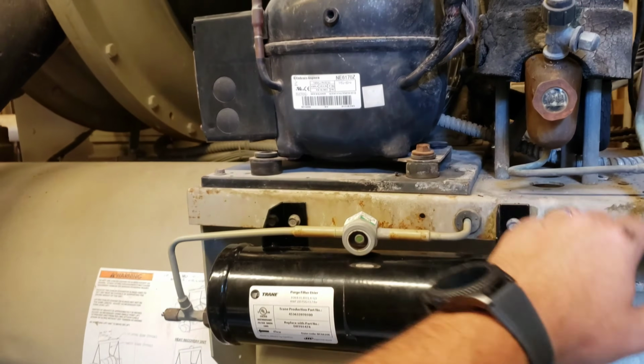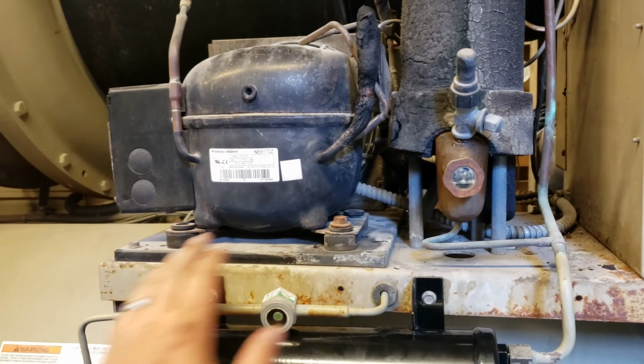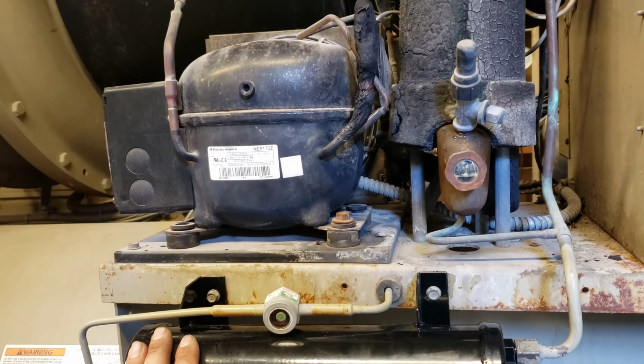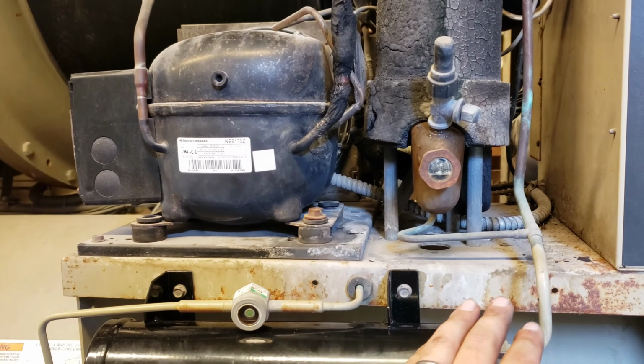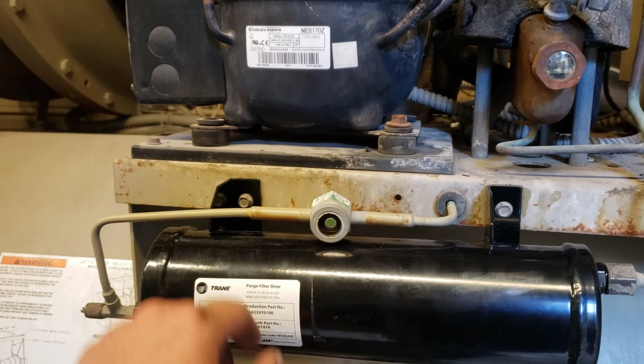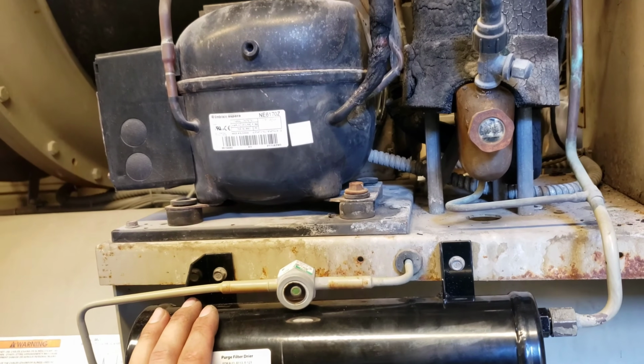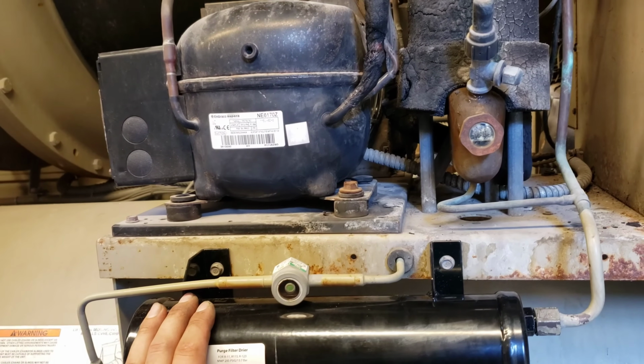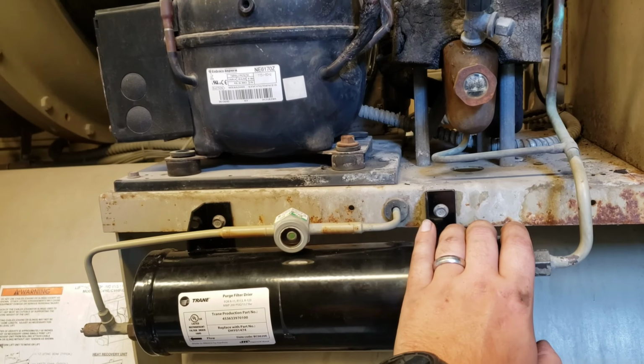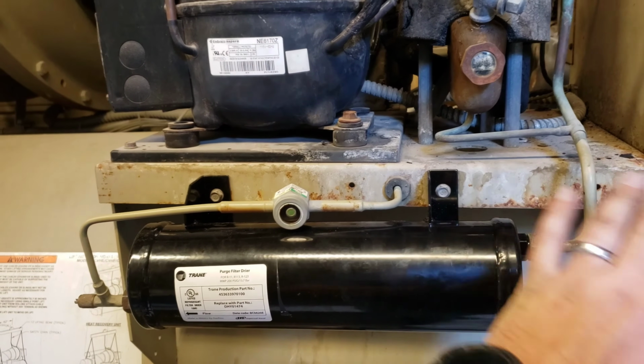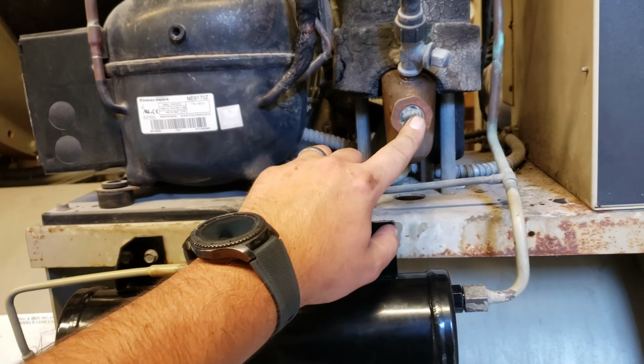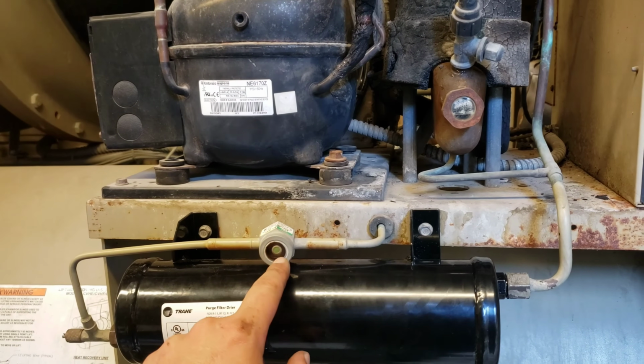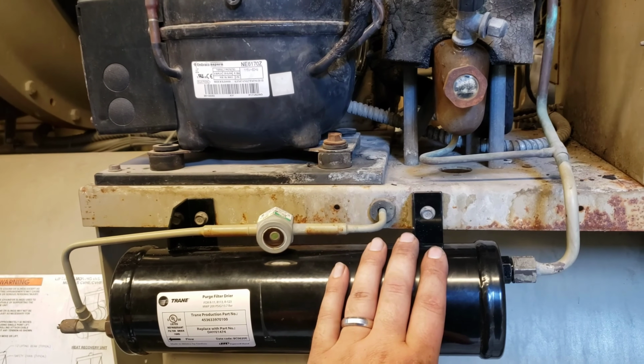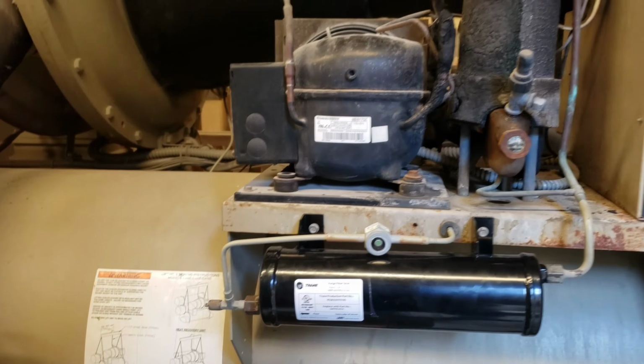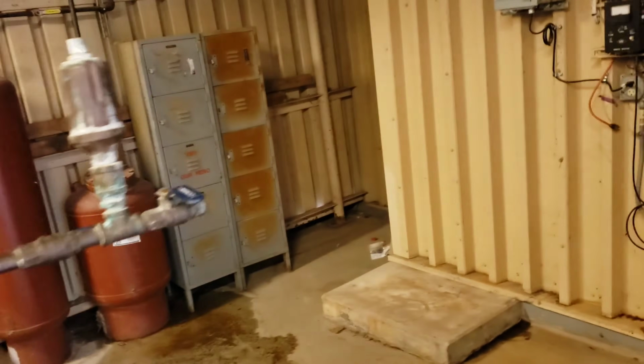Anyway, on top of that, even after I got the purge running, I was not draining the liquid off of the tank like I was supposed to. And come to look at the date code, the date code on the purge filter was from 2014. Well, it's 2020. So I already had the new filter ready to go. I just hadn't installed it yet. I went ahead, put it in. That took care of that. Now it's draining fine. My liquid level's doing fine. I can see it purging down and draining through my sight glass without any issues. So I'm really happy with that now. Anyway, I have no idea what else I'm going to run into.